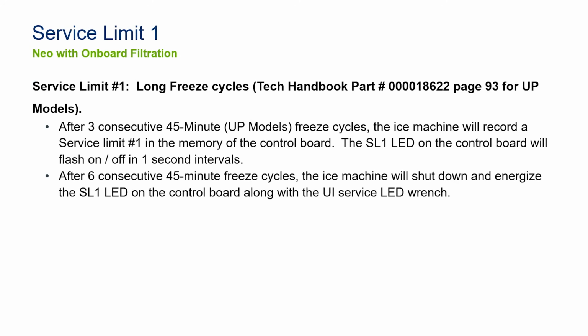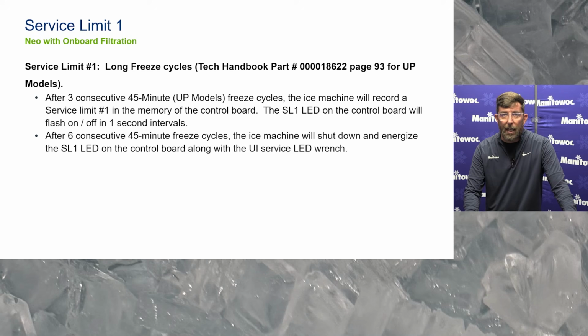So what is service limit number 1? Service limit number 1 is a long freeze shutdown. We've been doing service or safety limits, depending on the vantage and vintage of the machine, for years. Service limit number 1 is a long freeze. On NEO units with onboard filtration, running on R290 refrigerant, should you have 3 consecutive 45-minute freeze cycles, that's the key there. The maximum freeze on the new NEO with onboard filtration is 45 minutes.